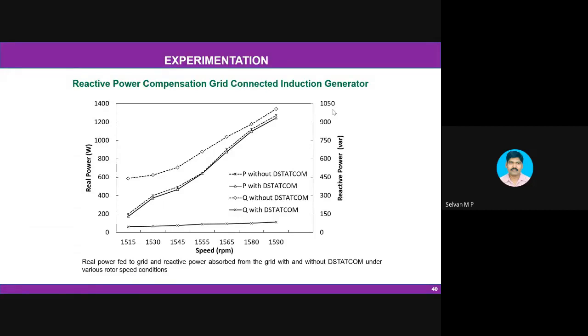So if you provide that by the STATCOM, then the STATCOM is providing the reactive power required by the machine. So from the grid, we are not drawing anything. So power factor will be improved, and the burden on the grid is getting reduced. Since you are reducing the burden on the grid, the voltage profile of the grid will be better. Otherwise, the voltage profile will go down. Here I am talking in terms of watt because the experiment is taken in the laboratory. In the actual field, it will be in megawatt, right?